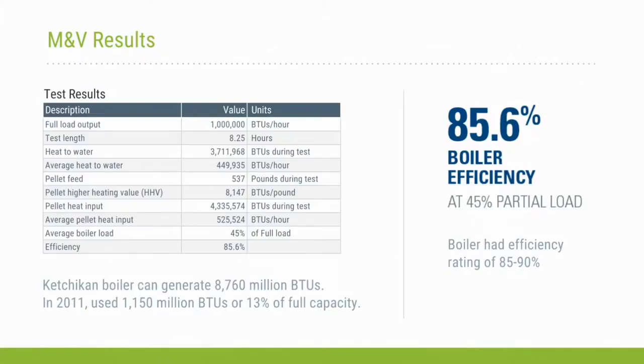And then we also sent a sample of the pellets out to a laboratory to find out exactly what their heating value was. So once you have, in essence, the amount of pellets in and their heating value, that's the heat input to the system. Since we measured the flow of the water and the difference in temperatures, we knew the heat output of the system. So the heat output divided by the heat input gives you the efficiency of the boiler system.